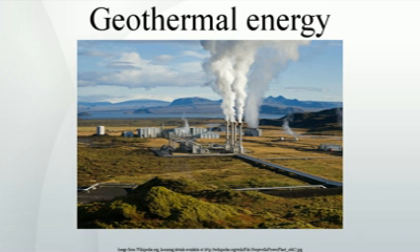The thermal efficiency of geothermal electric plants is low, around 10 to 23%, because geothermal fluids do not reach the high temperatures of steam from boilers. The laws of thermodynamics limit the efficiency of heat engines in extracting useful energy. Exhaust heat is wasted, unless it can be used directly and locally, for example in greenhouses, timber mills, and district heating. System efficiency does not materially affect operational costs as it would for plants that use fuel, but it does affect return on the capital used to build the plant.